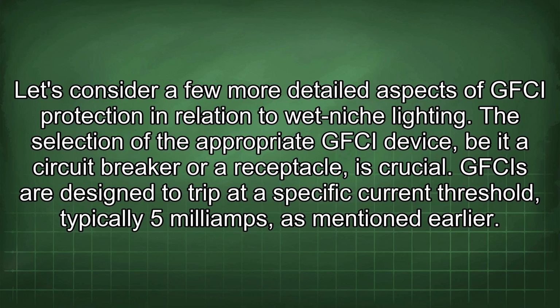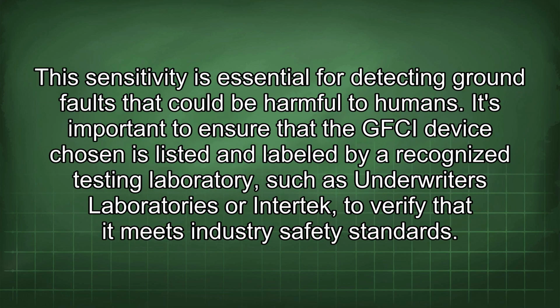The selection of the appropriate GFCI device, be it a circuit breaker or a receptacle, is crucial. GFCIs are designed to trip at a specific current threshold, typically 5 mA, as mentioned earlier. This sensitivity is essential for detecting ground faults that could be harmful to humans. It's important to ensure that the GFCI device chosen is listed and labeled by a recognized testing laboratory, such as Underwriters Laboratories or Intertek, to verify that it meets industry safety standards.